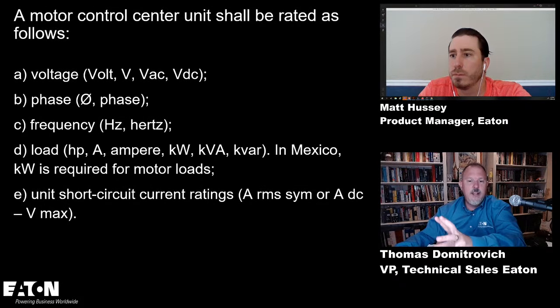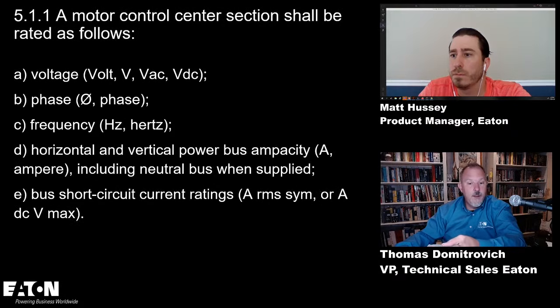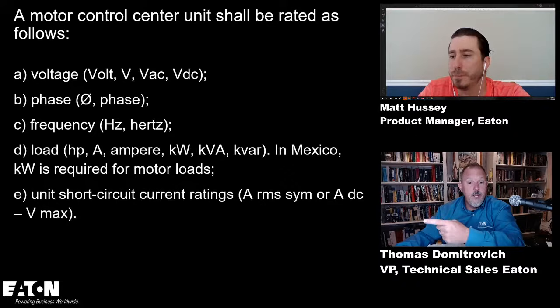These are all the things that have to be marked and how they're supposed to be rated. A motor control center section shall be rated as follows: voltage, phase, frequency, and the bus short circuit current ratings, the horizontal and vertical bus ampacities, which we just saw in that label previously. And then the motor control center unit, which is the bucket, has to have the voltage, phase, frequency, the load, and then in Mexico, kilowatts is required, and then the unit short circuit current rating. So each bucket will have a short circuit current rating as well, right?